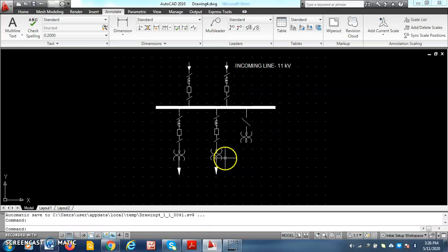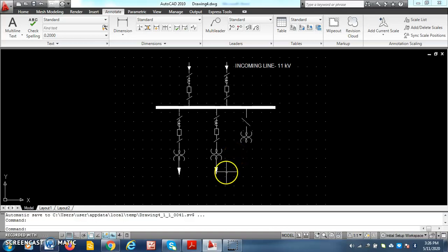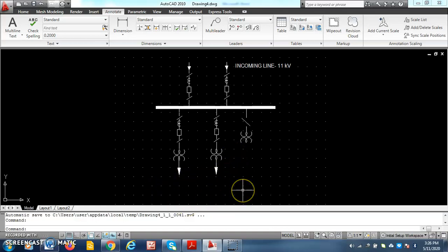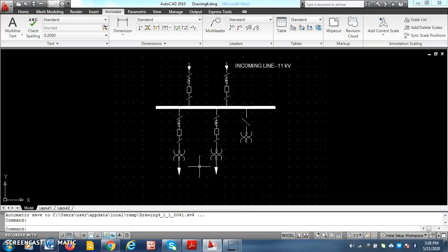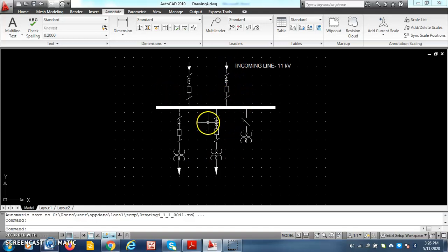The transformer. What rating is given in the problem statement? That has to be written here. 5MVA, 11kV star, bar, 6.6kV star, outgoing feeder, 6.6kV. All these things have to be written once the single line diagram is drawn. Annotation is very important. That has to be done with the multi-line text.